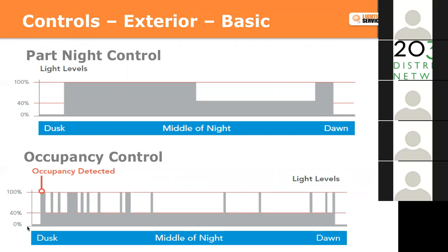There are other ways to control this. Part night control is basically a pre-programmed photocell. All these photocells look relatively similar, but they do different things. As opposed to a traditional photocell, a part night control cell turns the lights on at dusk and then dims them roughly halfway through the night to save more energy. The nice thing is they automatically adjust to seasonal time changes, reducing the maintenance of resetting a time clock or replacing photocells as they go bad.